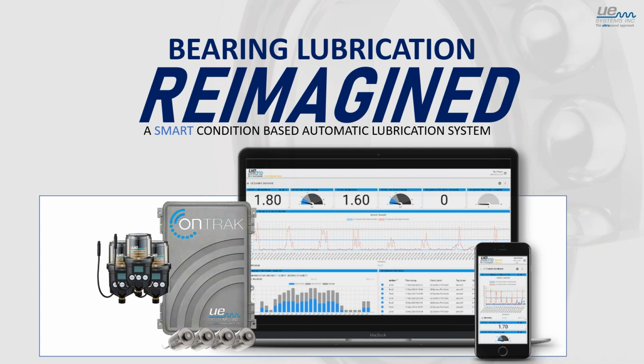Now, when it comes to the bearing itself, there's a recent academic paper from a local university, which I can send you, where they studied the incipient fault, and ultrasound comes out as the earliest to detect it. Sometimes it doesn't give enough information at that point to diagnose the exact issue, whereas with vibration you can go further. You're not going to do an ODS with ultrasound and things like that.